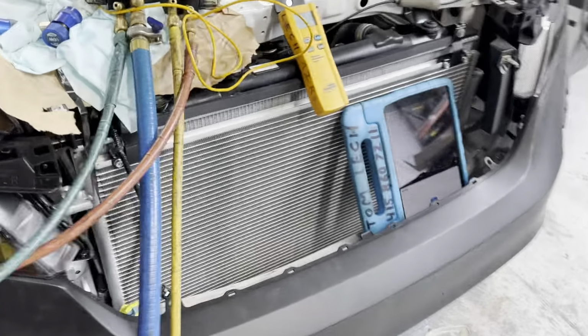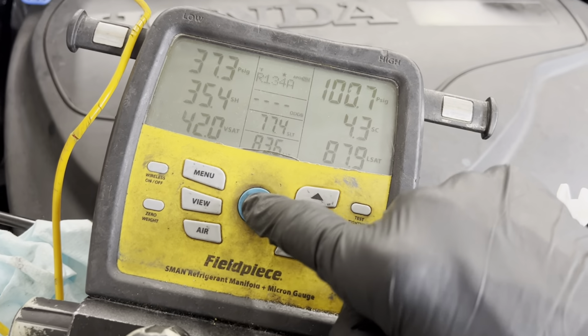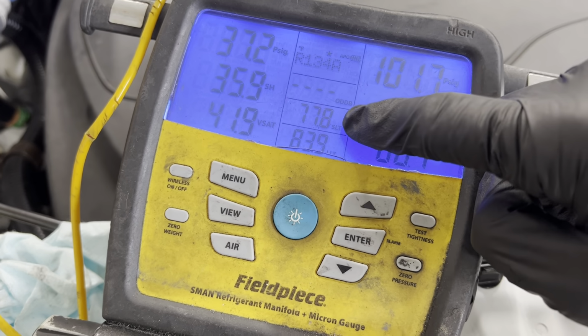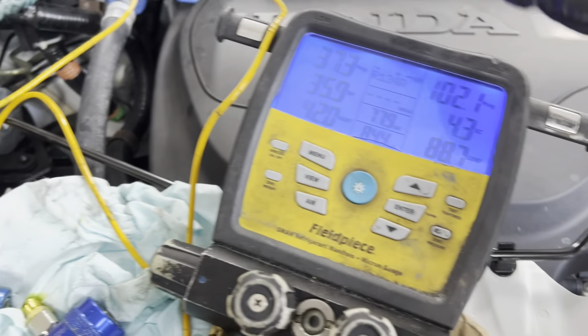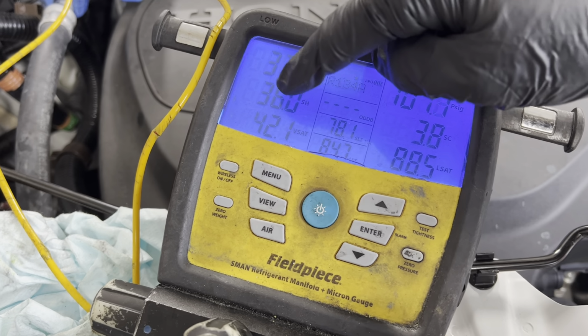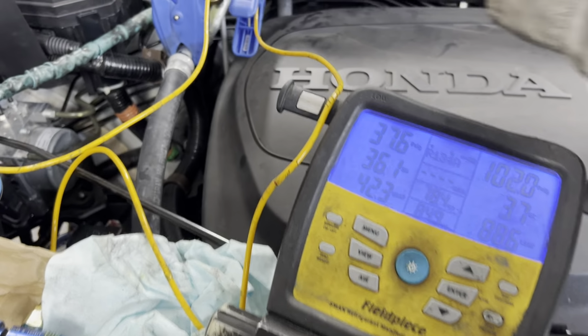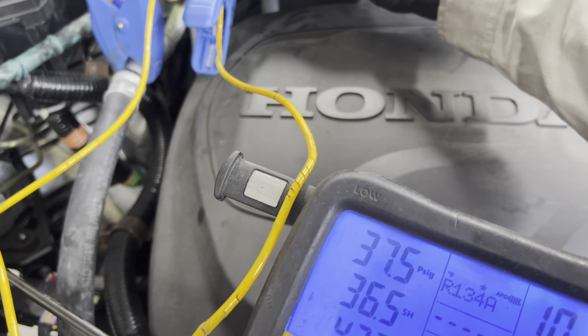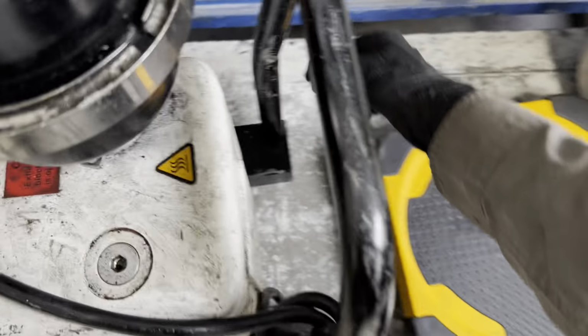Now we could look at our superheat. Now we can look at our suction line temperature. Okay, so now our suction line temperature is 77 degrees right here. 36 degrees superheat at this point, because it's picking up the heat energy that is absorbed through the suction line through the internal heat exchanger. Now, I'm gonna use this as something to stand on. I'm gonna see if I could reach down there. Let's take this suction line temperature. And I want to make sure the sensor's not pointing towards the hot exhaust.